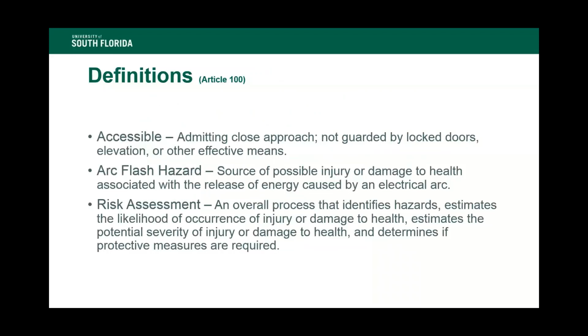Some definitions - and these are only a few of the very many in the standard. Accessible: they spell out what accessible means by basically saying it admits close approach. You can come up close to a piece of equipment of an electrical nature, but only under certain conditions, which are spelled out later. It also describes accessible as not being guarded, or by locked doors or elevation or other effective means - in other words, the person ought to be able to walk right up to the electrical equipment without really any hindrance.